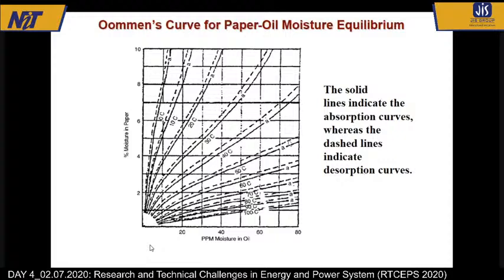two curves, solid curve and dotted curve. That means one is for temperature decrease, and temperature decreasing is always slightly higher. And as you can see, let's say at 0 degree centigrade, moisture in paper is high and moisture in oil is low. That means when the temperature falls, moisture moves from oil to paper. Whereas at high temperature you can see oil is high and paper is low, because moisture has moved from paper to oil.